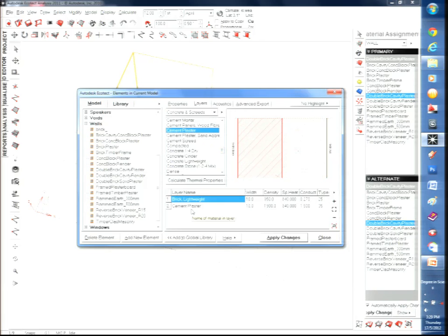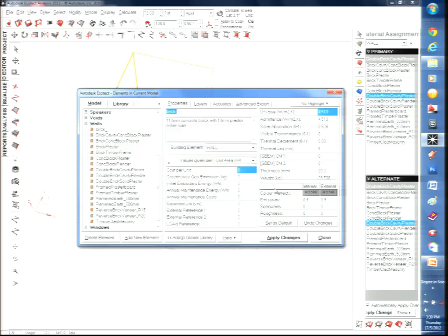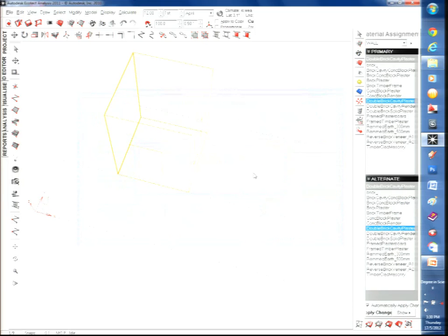After assembling the layers, press 'Calculate Thermal Properties.' Ecotect will compute the U-value and other values. The thermal lag — which represents thermal mass — is particularly important. It is the time delay between the maximum outdoor temperature (e.g., at 1 p.m.) and the maximum indoor temperature (e.g., at 4 p.m.), meaning heat takes about 3 hours to conduct through the wall. This directly affects room temperature calculations.